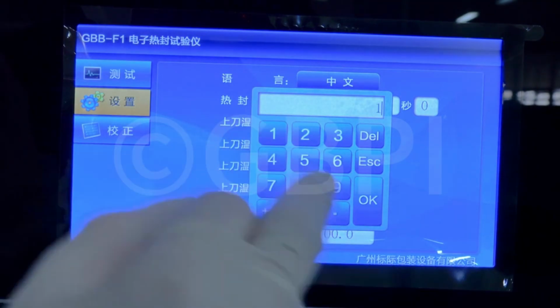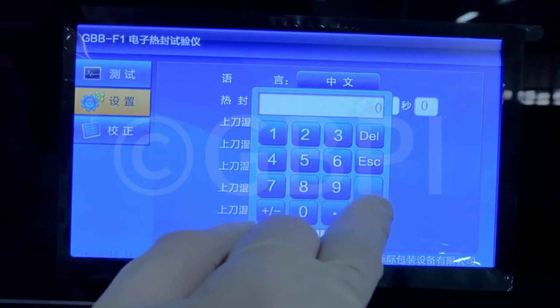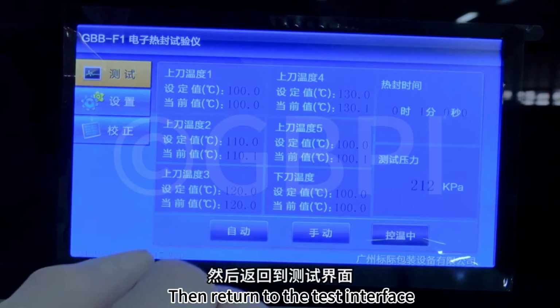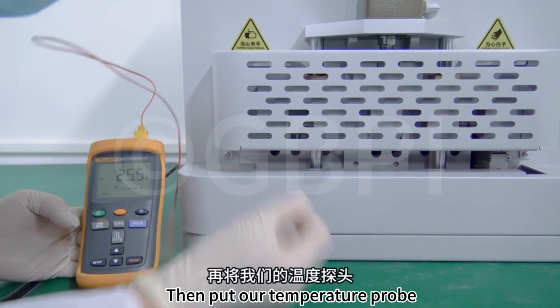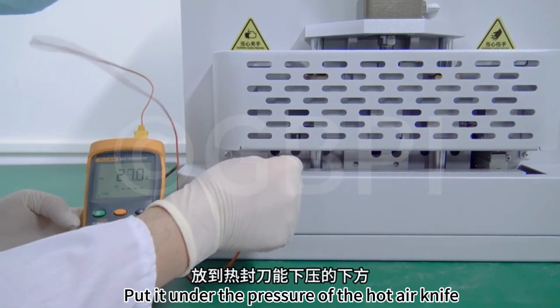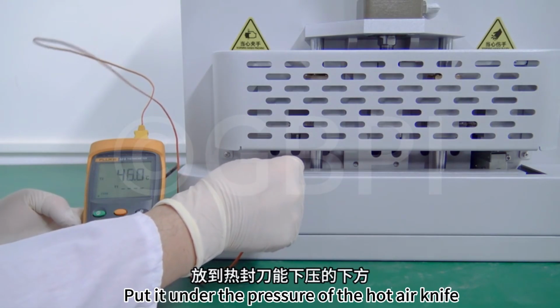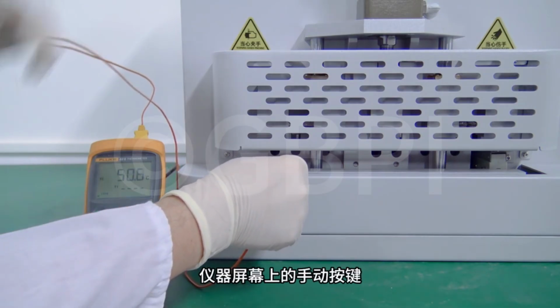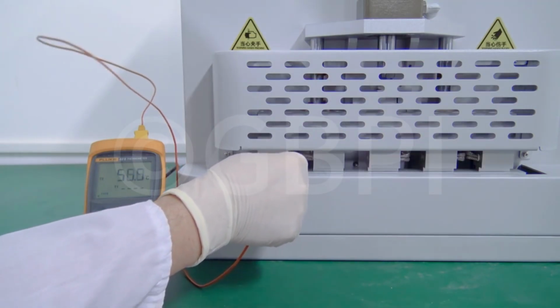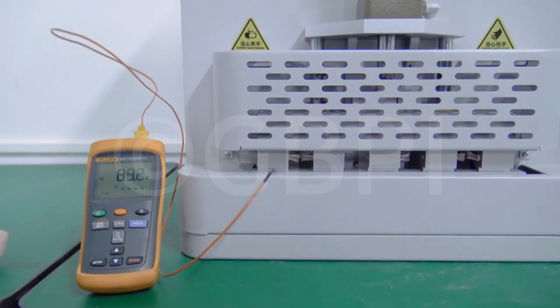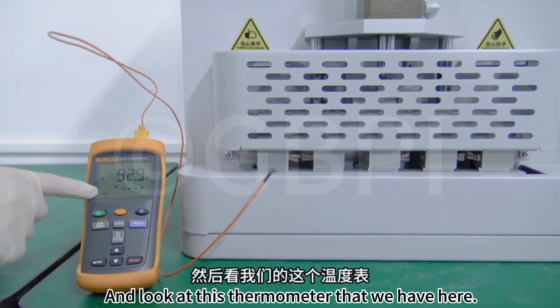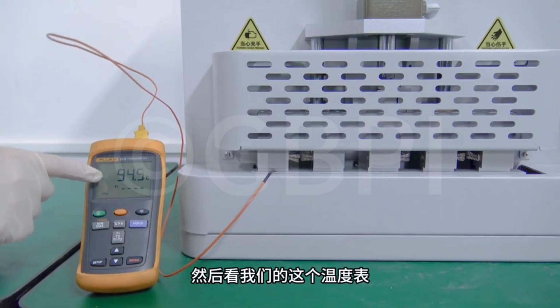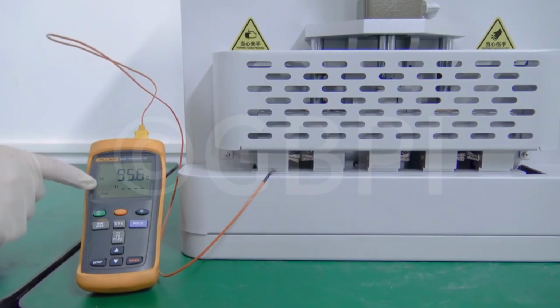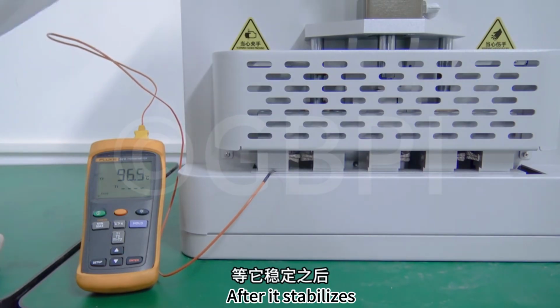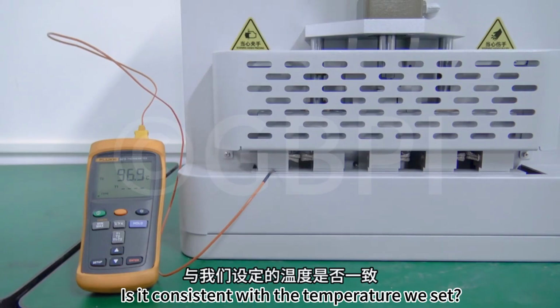Change the hot air time to 1 minute in the settings. Then return to the test interface. Then put our temperature probe. Put it under the pressure of the hot air knife. Manual buttons on the instrument screen. Then hold down. And look at this thermometer that we have here. The actual displayed temperature. After it stabilizes, is it consistent with the temperature we set?